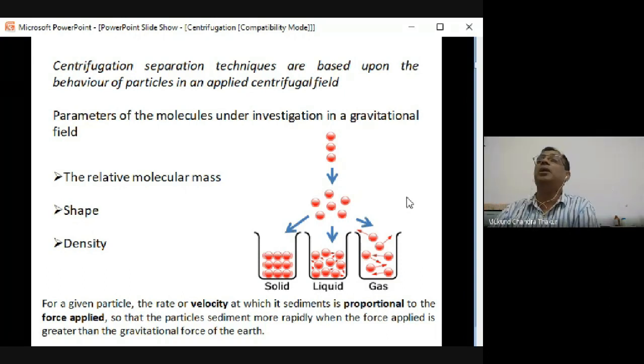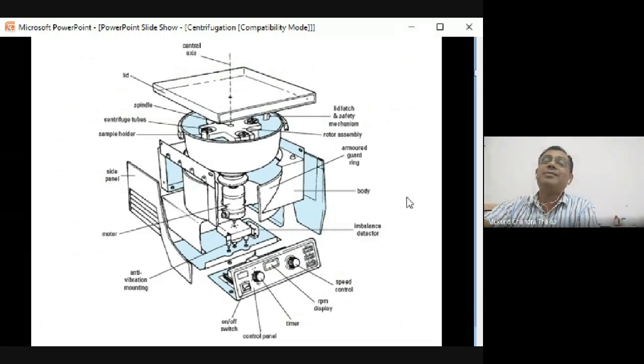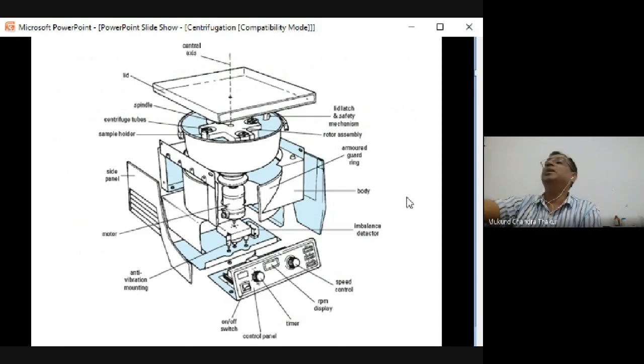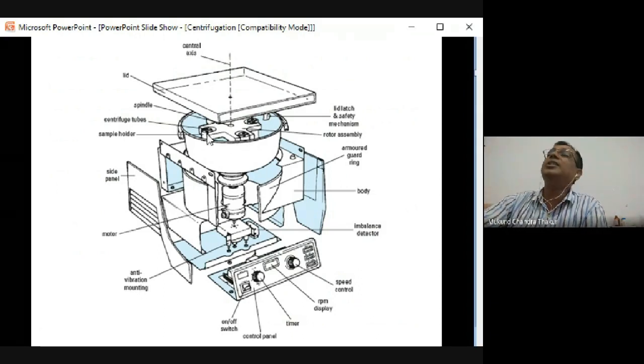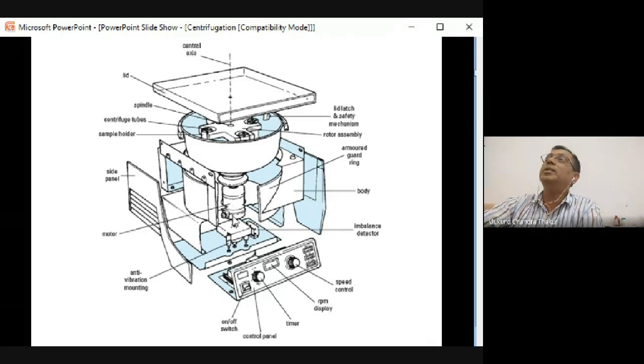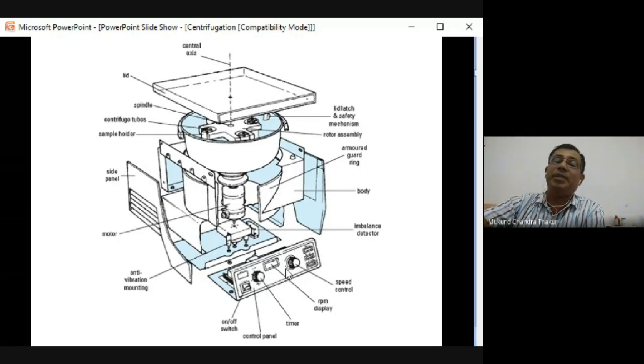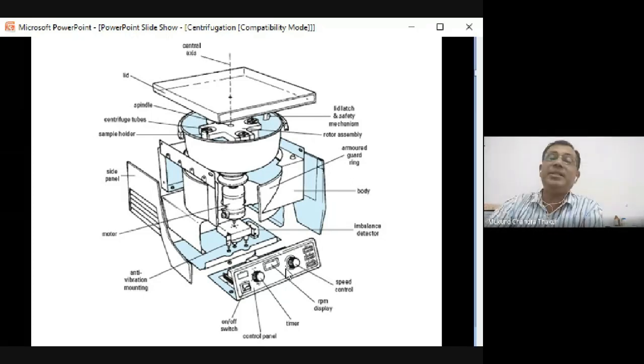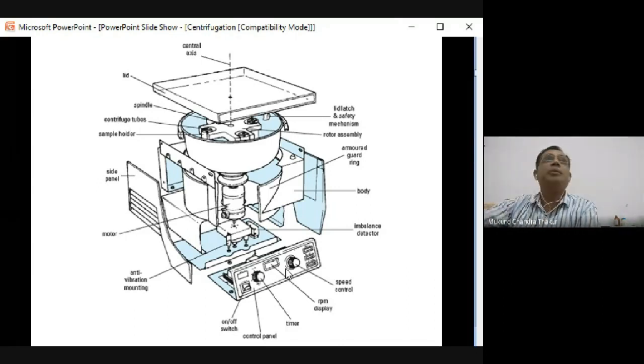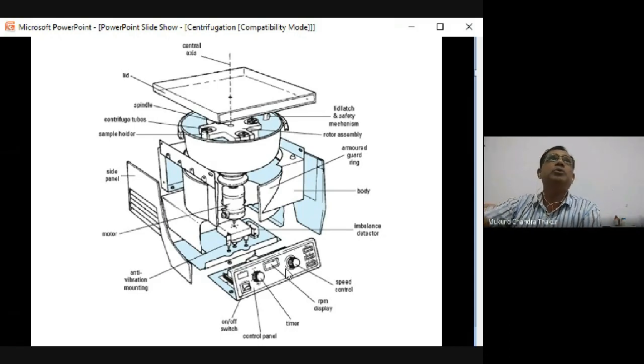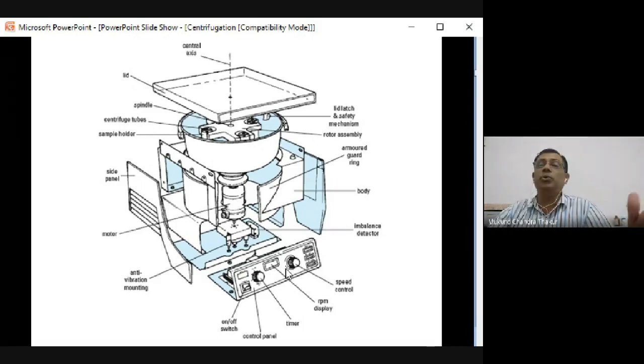The centrifuge machine applies an external force under which particles are separated. The rotor has places where you put centrifuge tubes; this rotor is connected with a motor. Different parameters like time and force can be adjusted and programs saved - for example, a two-hour or 30-minute program at 16,000 RPM or 2,000 RPM. You can vary the time and RPM, but at any given run you fix both.